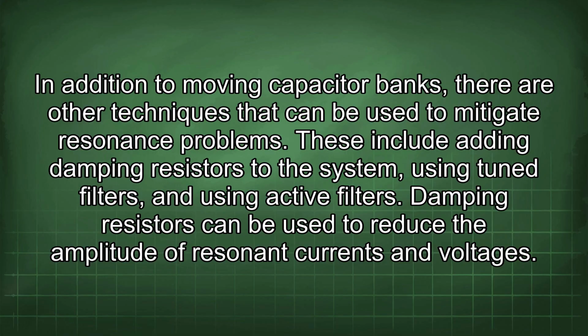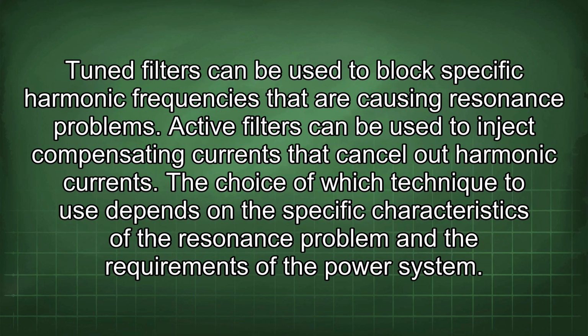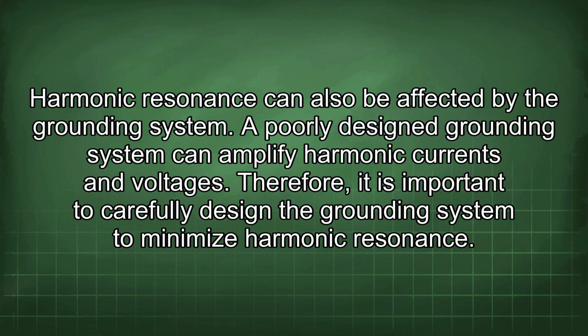Damping resistors can be used to reduce the amplitude of resonant currents and voltages. Tuned filters can be used to block specific harmonic frequencies that are causing resonance problems. Active filters can be used to inject compensating currents that cancel out harmonic currents. The choice of which technique to use depends on the specific characteristics of the resonance problem and the requirements of the power system. Harmonic resonance can also be affected by the grounding system.